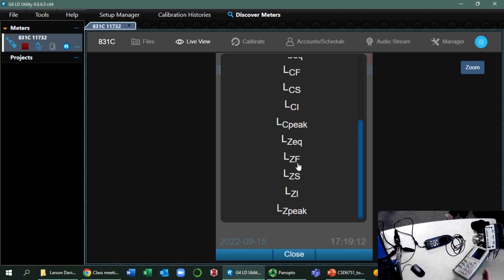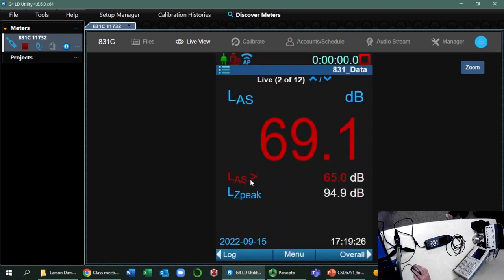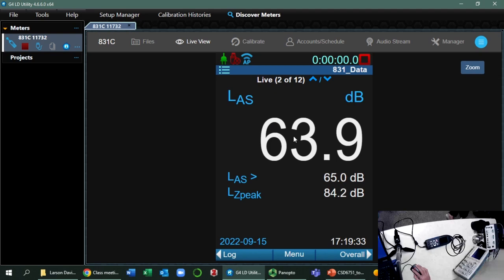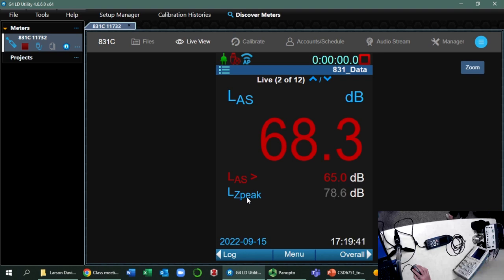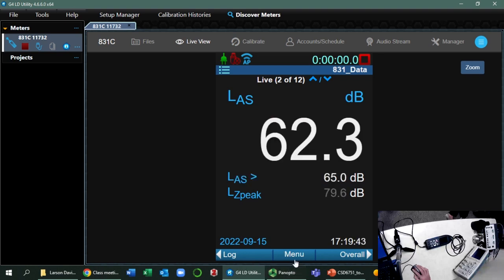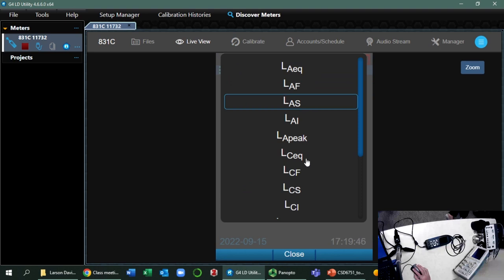For research lab calibration, especially calibrating an audiometer, we want frequency-specific measurement, so we look at the Z weighting, but I'll show both so you see how it goes. Here it shows the numbers—actually three. LAS, LA here is 66 because I'm talking, and then LZ, which is the Z weighting. Let me change it to LZ, and then set it to slow.